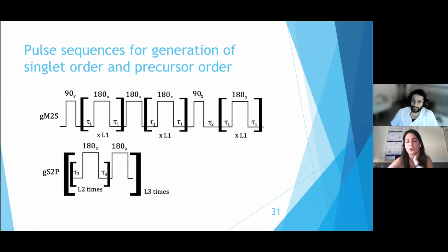Okay, so do you compensate for the power dissipation, or is it heating up your sample a lot if you do a lot of loops? So luckily for us, doing liquid state NMR, that's never really a problem. We never really experienced heating problems with these long loops. The problems you do experience tend to be when you're doing spin locking, so strong spin locking to basically suppress the symmetry breaking terms. Yeah, that tends to be the big killer.